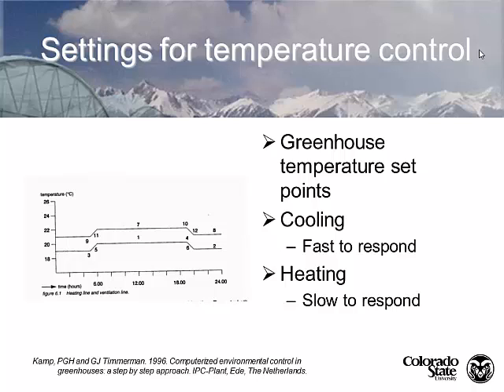What some people will do is set their cooling system to respond quickly — setting the set points closer on the cooling side. These numbers represent deviations from the set point. We'll often design our heating system to respond more slowly, with wider gaps, because the thermal mass of benches, floors, and plants absorbs heat and we want the heating system to respond slower.